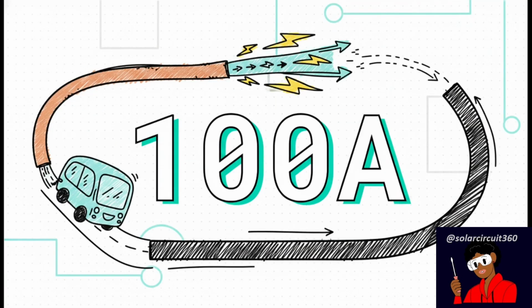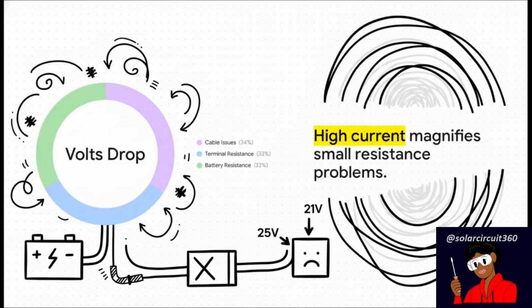To put that into perspective, let's use the DC power formula. A 2400-watt load on a 24-volt system requires a massive 100 amps of continuous DC current. 100 amps! That is a ton of electrical traffic trying to squeeze through your cables all at the very same time. And this brings us right to the absolute core of the issue: voltage drop. When you're pushing those kinds of high current levels, even the tiniest bit of resistance becomes a huge deal. We're talking undersized cables, a slightly loose terminal, or maybe just aging batteries.